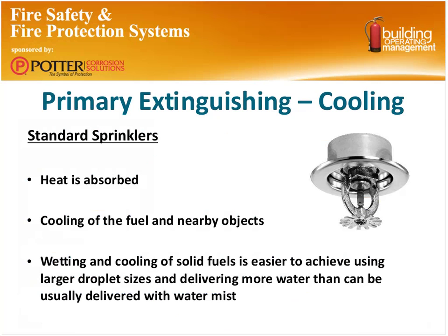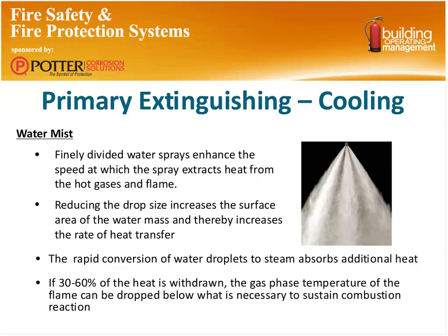Not much different than the way a sprinkler system works. A standard sprinkler really fights a fire by, one, absorbing heat, two, cooling the objects nearby, and three, wetting. You can't beat the way a sprinkler wets Class A combustibles. So if you have a lot of Class A combustibles, like a lot of wood, plastics, any other Class A product, typically the solid fuels are better wetted by the large droplet of a traditional sprinkler system.